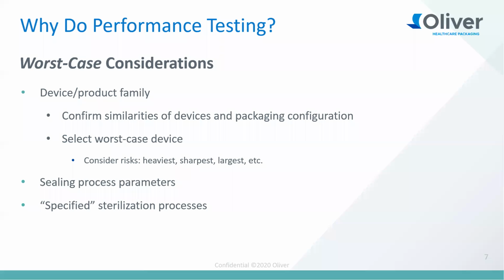Yeah, thanks, Tommy. So for the worst case considerations here, in my experience, I like to start with defining the device and product family itself. So you have to confirm the similarities of devices and packaging configuration. For example, there are times where a device may have the same description as another, but they could be a completely different type, like a different type of plastic, maybe a hard versus soft. And you really want to pay attention not only to the description and how they're used, but the profile and all the characteristics of the devices to define that family. And then out of that family, you're allowed to select a worst case device and packaging configuration to represent that entire family in this testing sequence we're going to go through in this webinar.